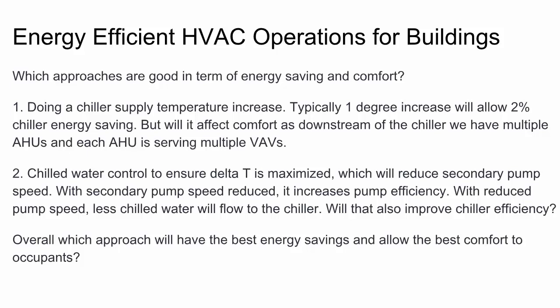And the second idea, chilled water control to ensure delta T is maximized, which will reduce secondary pump speed. With secondary pump speed reduced, it increases pump efficiency. With reduced pump speed, less chilled water will flow to the chiller. Will that also improve chiller efficiency?